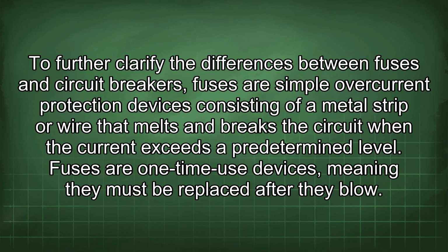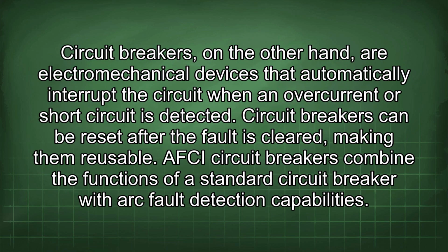To further clarify the differences between fuses and circuit breakers, fuses are simple overcurrent protection devices consisting of a metal strip or wire that melts and breaks the circuit when the current exceeds a predetermined level. Fuses are one-time use devices, meaning they must be replaced after they blow. Circuit breakers, on the other hand, are electromechanical devices that automatically interrupt the circuit when an overcurrent or short circuit is detected. Circuit breakers can be reset after the fault is cleared, making them reusable. AFCI circuit breakers combine the functions of a standard circuit breaker with arc fault detection capabilities.